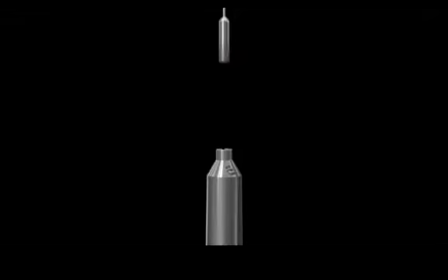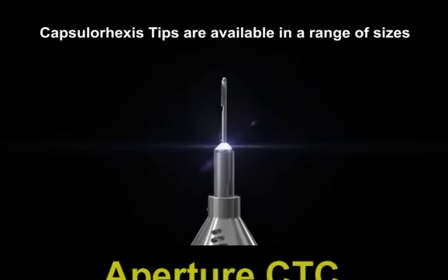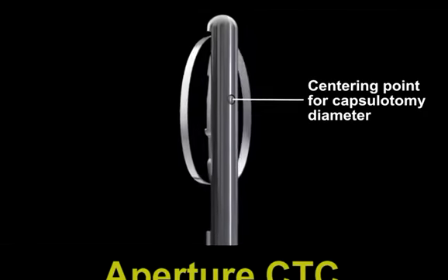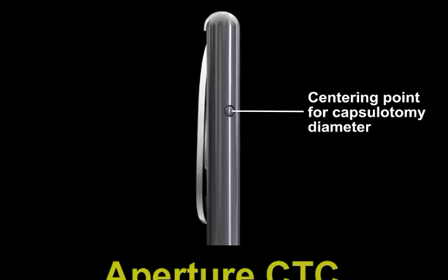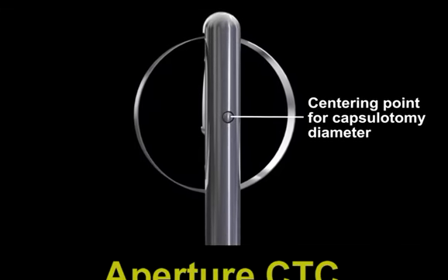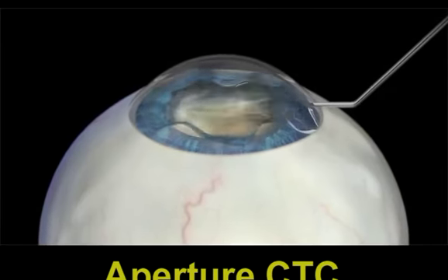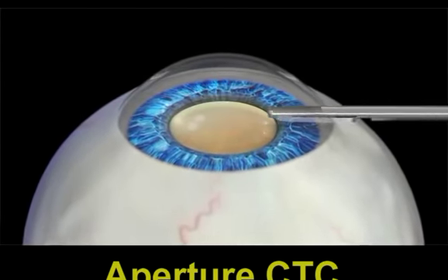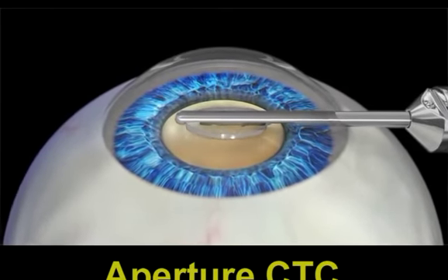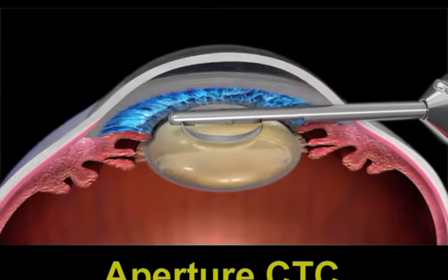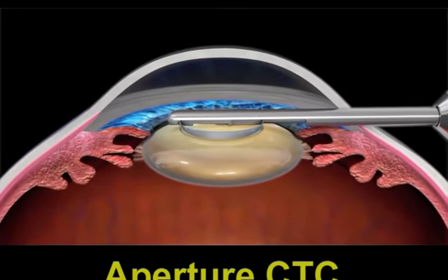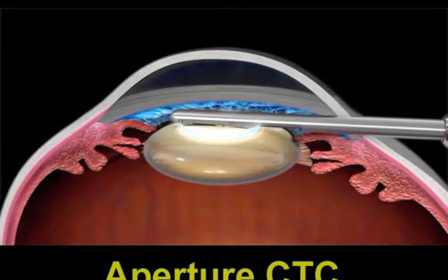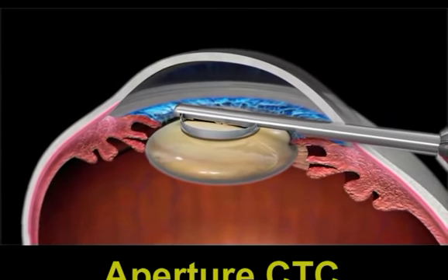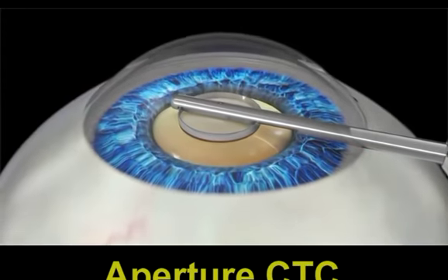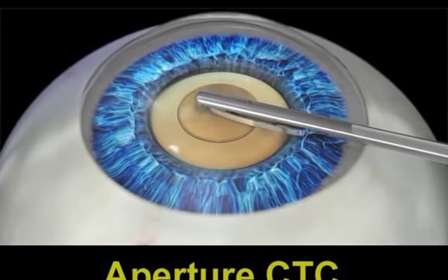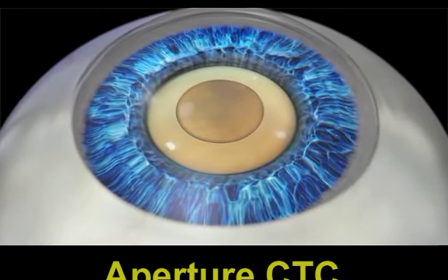The other device in the pipeline is the aperture CTC. It has tips of various sizes. This is the tip, and this is the centering point for centering the diameter of the capsulotomy. The advantage with all these new devices is that the capsulotomy can be well positioned under direct visualization through the microscope, so it can be very well centered. The aperture CTC, or the continuous thermal capsulotomy, works through a steel ring, and it is a non-laser based system. Continuous controlled low-level energy is provided to the cutting elements on the steel ring, and this creates a smooth, repeatable, uniform capsulotomy or capsulorhexis in difficult cases of cataract also.